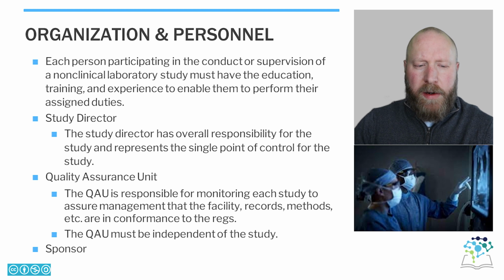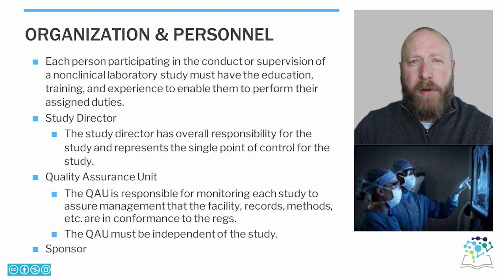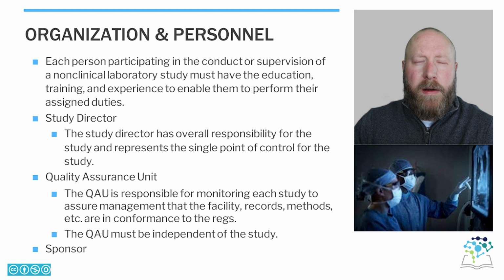In addition to the study director, the regulations will provide a QAU to provide independent oversight of your study. The QAU is really the FDA's eyes and ears for themselves while your study is being conducted. It's an independent body that will provide oversight and occasional audit of your study itself to assure that all the regulations are met and that all of your protocol elements have been executed as per the protocol.